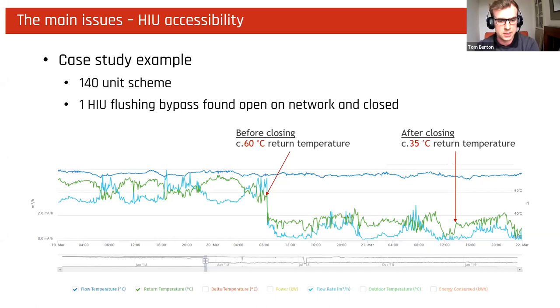And you can see, on the left-hand side you've got about a 70 degree flow temperature, and the return temperature is sitting at about 60-65 degrees, so really quite elevated. And then in the middle, at about 8 o'clock on the 20th of March, this was a couple of years ago, one bypass, which we'd identified through remote review of the data, we found that all of these performance issues were caused by this one bypass above an HIU.